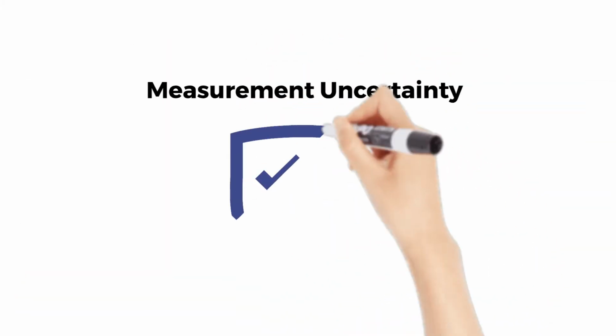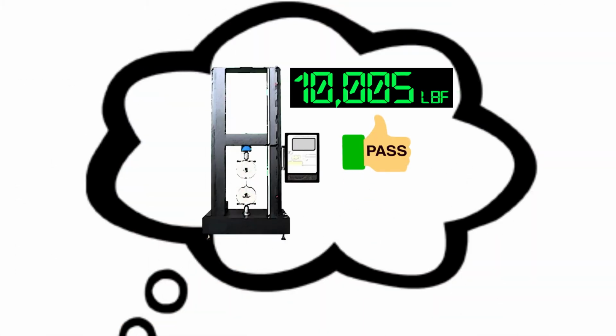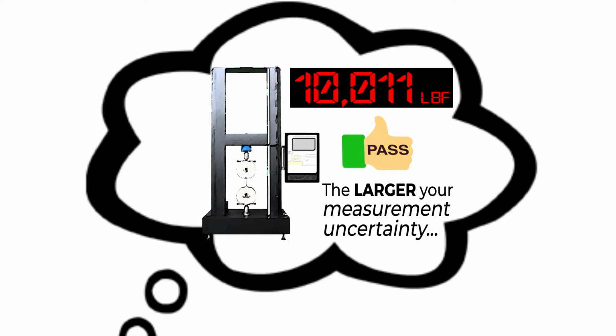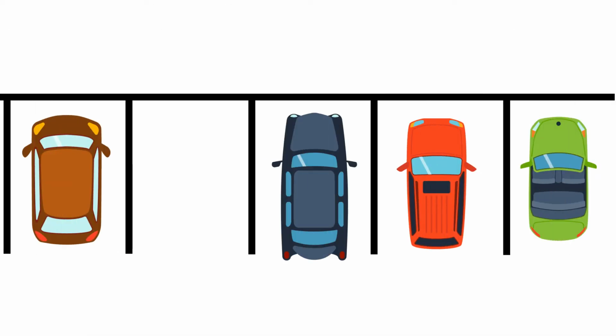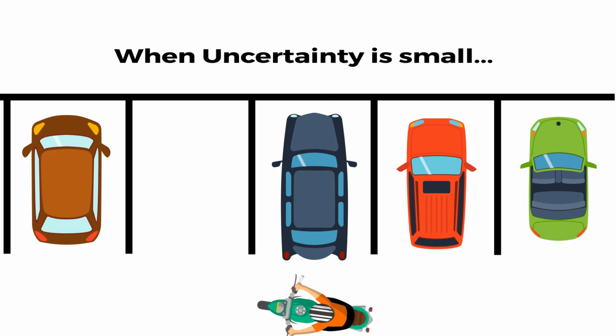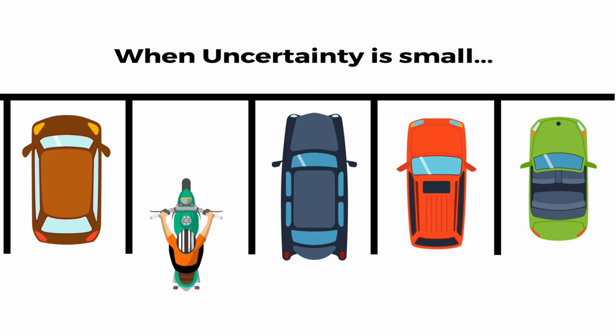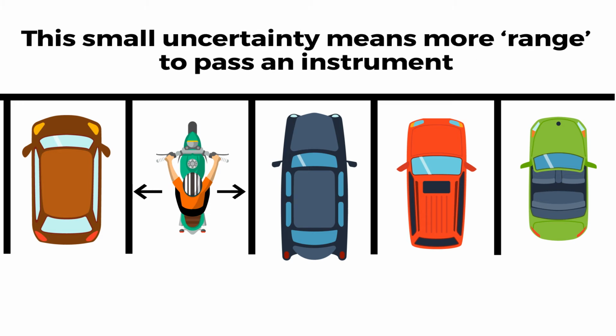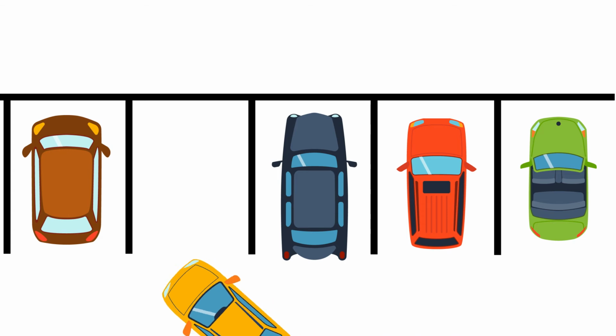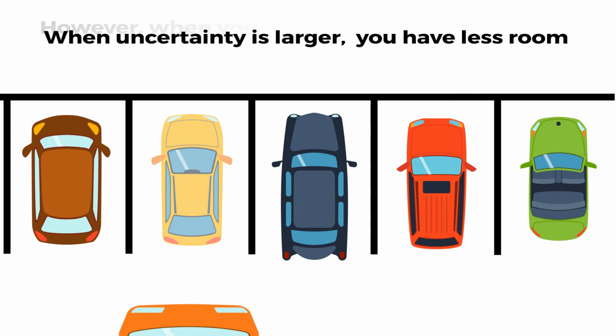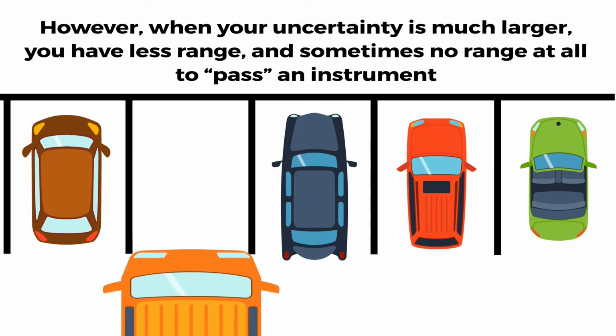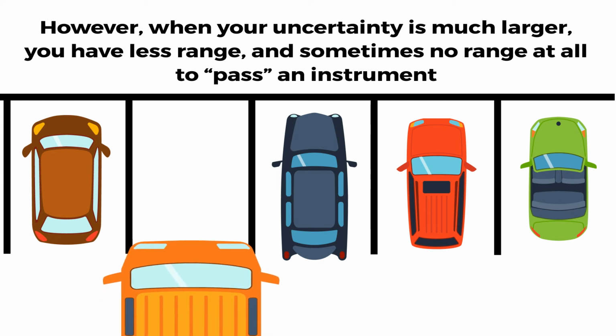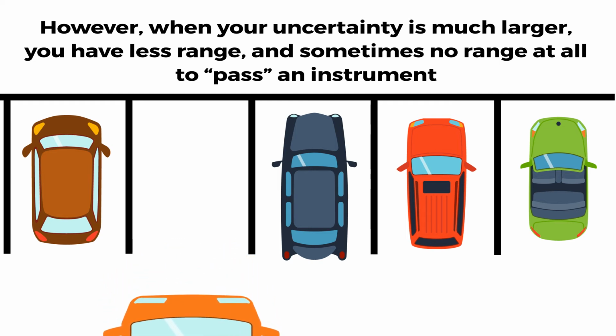Measurement uncertainty also keeps us honest. If we think about making a conformity assessment of pass or fail, the larger your measurement uncertainty, the more likely you are to fail an instrument. Using the analogy of a parking space, when your uncertainty is small, you have a parking space large enough to easily park. This small uncertainty means we have more space or range to pass an instrument. However, when your uncertainty is larger, you have less room. If the uncertainty is much larger, you have less range and sometimes no range at all to pass an instrument.